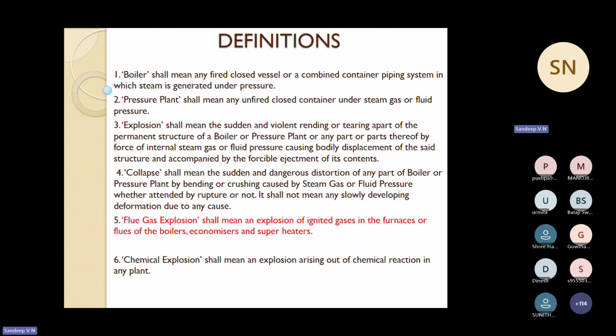If powdered coal is used as the fuel, sometimes the combustion products going to the atmosphere will carry powder of coal also. This powder will get deposited on the inner surface of the pipeline, or the powder may be in suspended form in the pipeline. When it reaches a particular temperature, it auto ignites, and then sudden expansion of combustion products can create an explosion in flue gas pipelines. So it is known as flue gas explosion. It is also covered under boiler pressure plant policy.